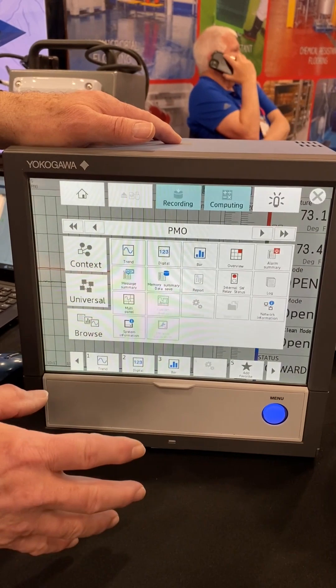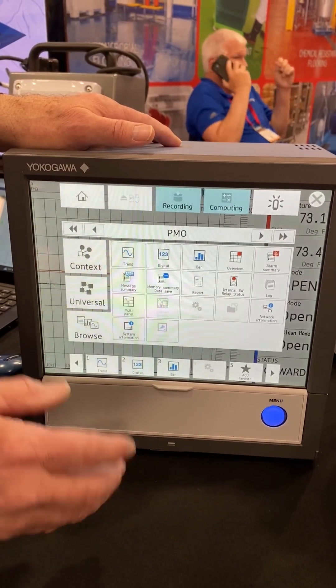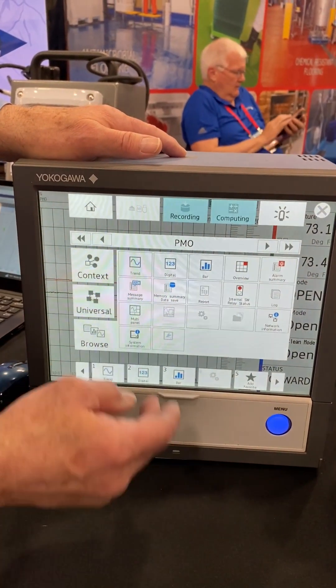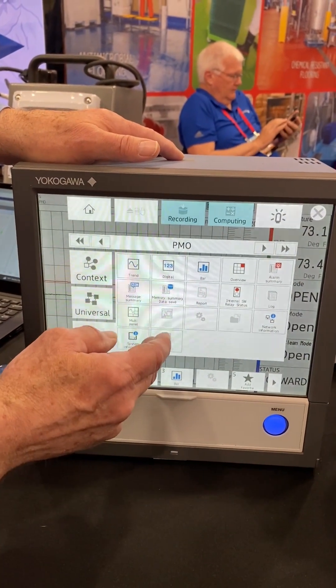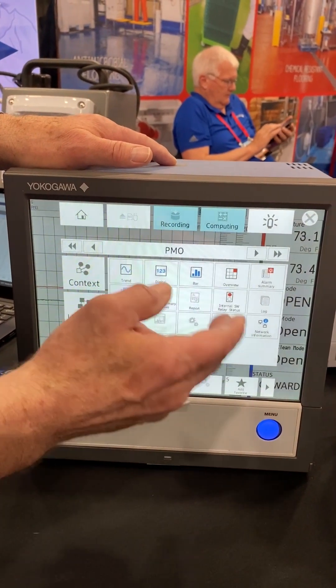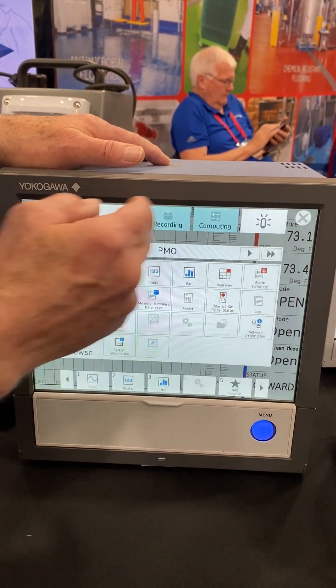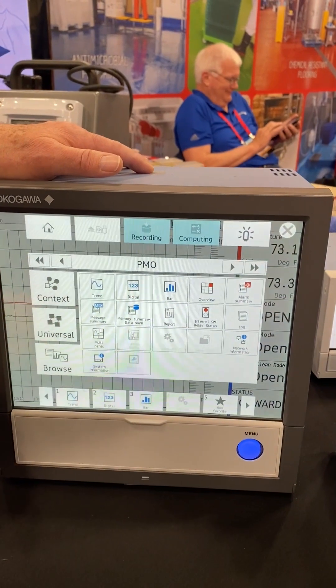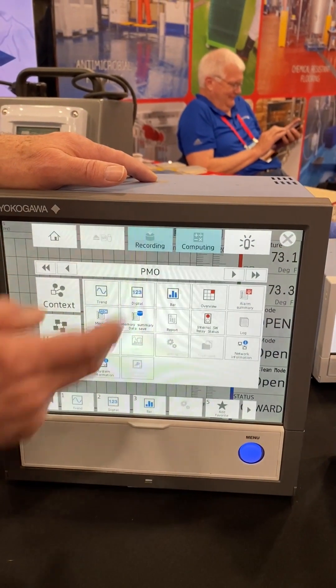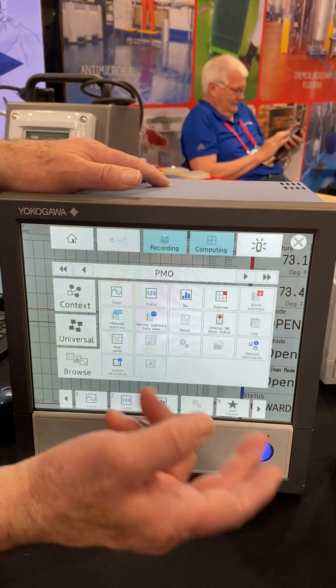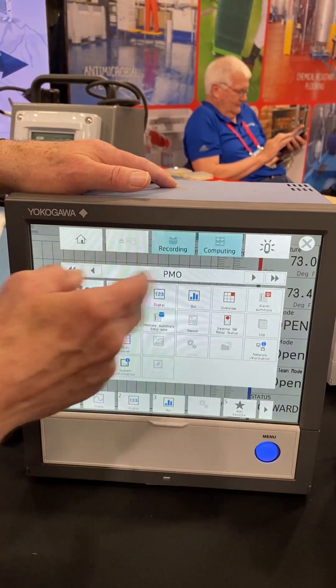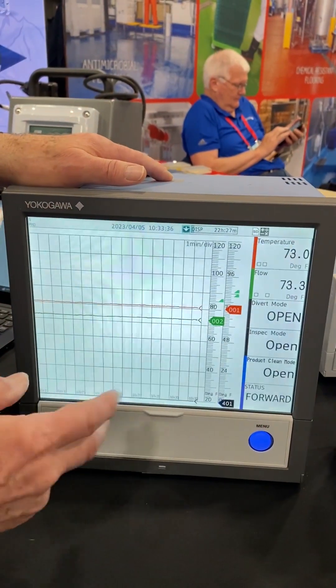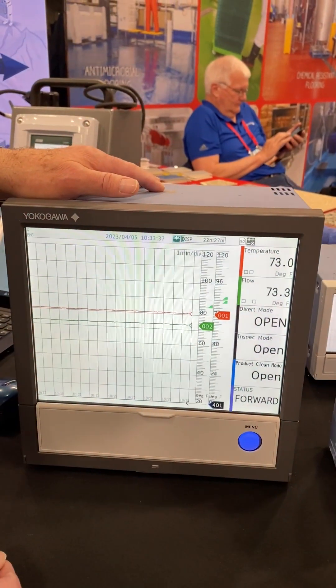you cannot go in and make any changes to the configuration, you can't change the clock, you can't change the recording status. You'll notice here these icons are now grayed out. I can hit this all day long and nothing's going to happen, because that's not available — the recorder is in regulatory lockdown mode.